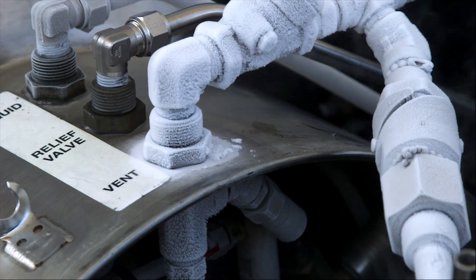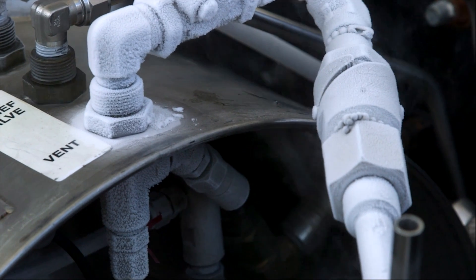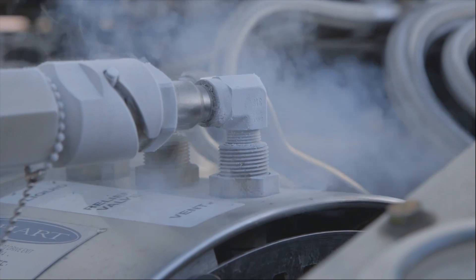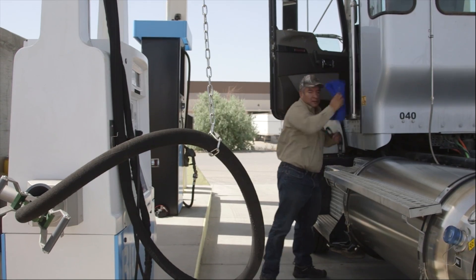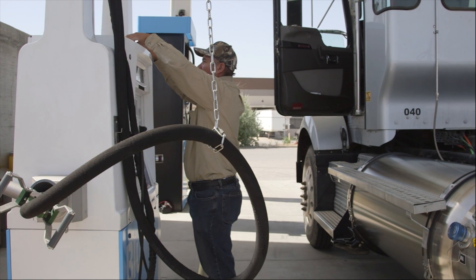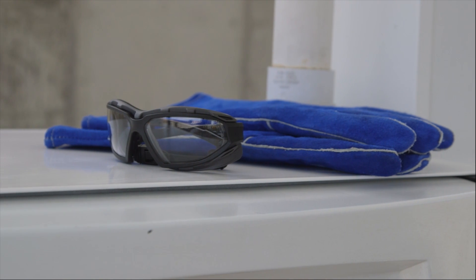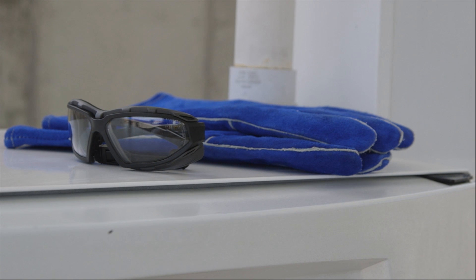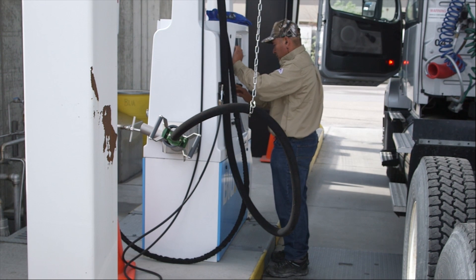Fueling an LNG-powered vehicle is not complicated, but LNG is stored at very cold temperatures, so you'll want to take a few precautions. Contact with extremely cold fuel or metal surfaces can cause freeze burns to exposed skin. To protect yourself, you'll wear personal protective equipment. A face shield or goggles protect your eyes from the potential but unlikely release of the super cold vapor or liquid. Thermally insulated gloves make it possible to handle the cold hoses and valves. A long-sleeved shirt, long pants, and leather shoes are recommended to protect your skin from accidental exposure.